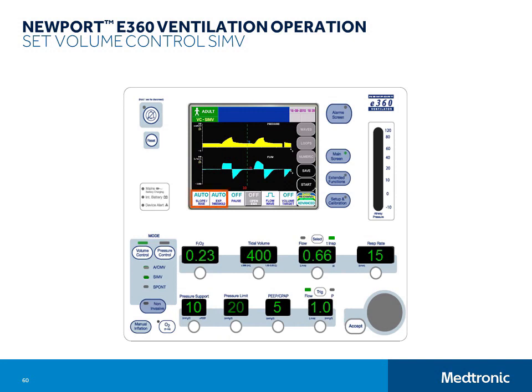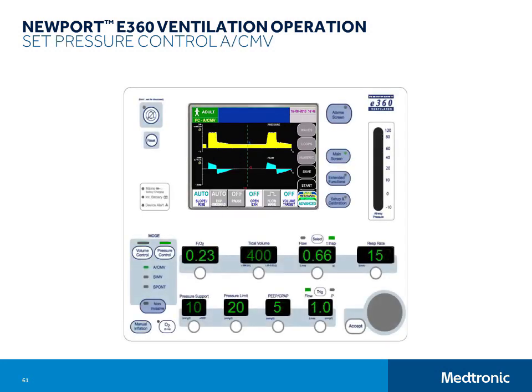Next, we'll switch to pressure control ACMV. Just push the pressure control button until pressure control ACMV is lit on the control panel. Then press accept. Notice that the pressure limit display lights up and the tidal volume display goes dim. But otherwise, many of the same settings like FiO2, respiratory rate, PEEP, and trigger are still lit and therefore need to be set. Set the inspiratory time. Set the pressure limit at the desired target pressure level above ambient. Remember, pressure limit sets a target pressure above ambient pressure. The peak pressure will not change if you change PEEP. This is opposite from pressure support, which sets a target change in pressure above PEEP.